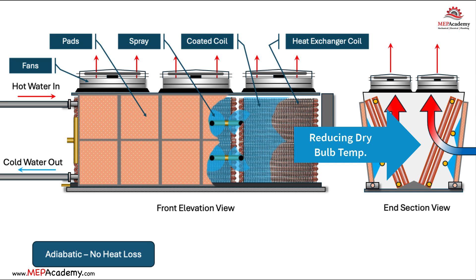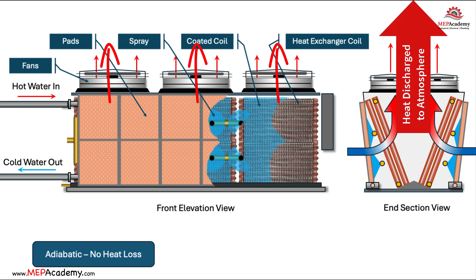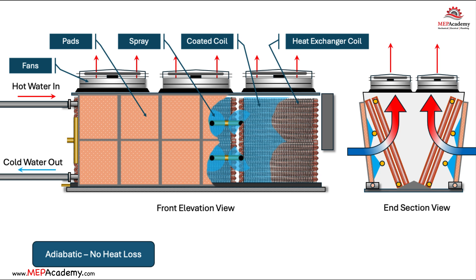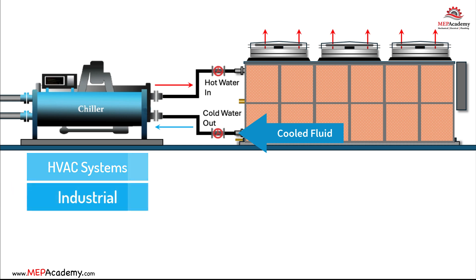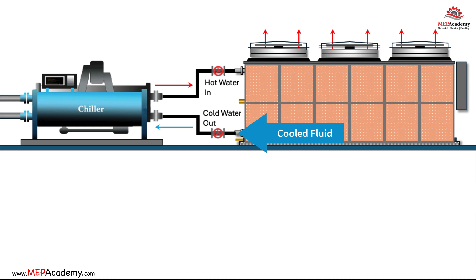This cooled air then passes over the surface of the heat exchanger, where it absorbs heat from the hot fluid inside the tubes and on the surface of the fins. The heat is then discharged to the atmosphere by fans at the top of the unit. As a result, the hot fluid inside the tubes loses heat to the cooled air through the heat exchanger, and the cooled fluid exits the adiabatic fluid cooler to be recirculated back into the system it is cooling, such as an HVAC system or industrial process.